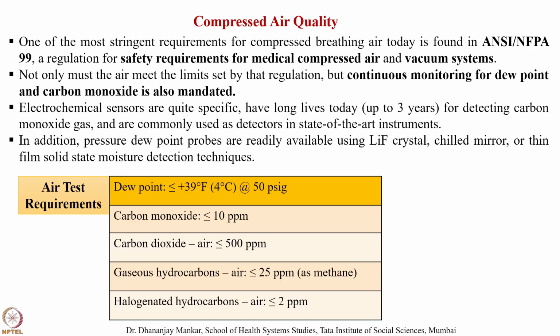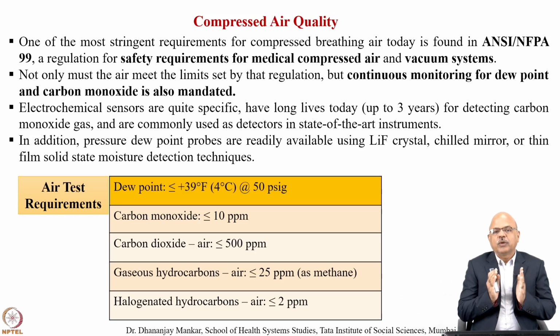Compressed air quality. One of the most stringent requirements for compressed breathing air today is found in ANSI/NFPA 99, a regulation for safety requirements for medical compressed air and vacuum systems. Not only must the air meet the limits set by the regulations, but continuous monitoring for dew point and carbon monoxide is also mandated.